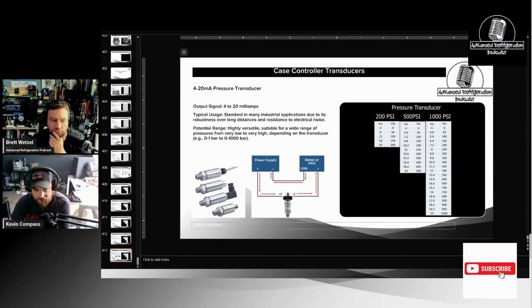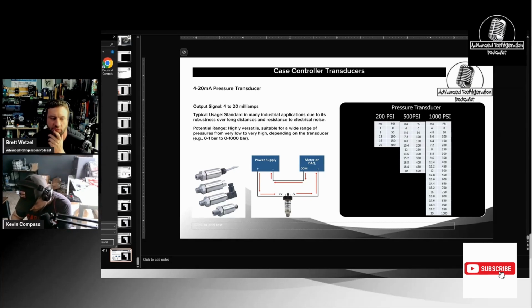So it's just like checking the 0 to 10 volts DC, except it's a little bit more steps because you have to wire your meter in series with it, and you have to set it up for milliamp control readings. Yes. Yeah. So I'm just going to bring this up here. See that.